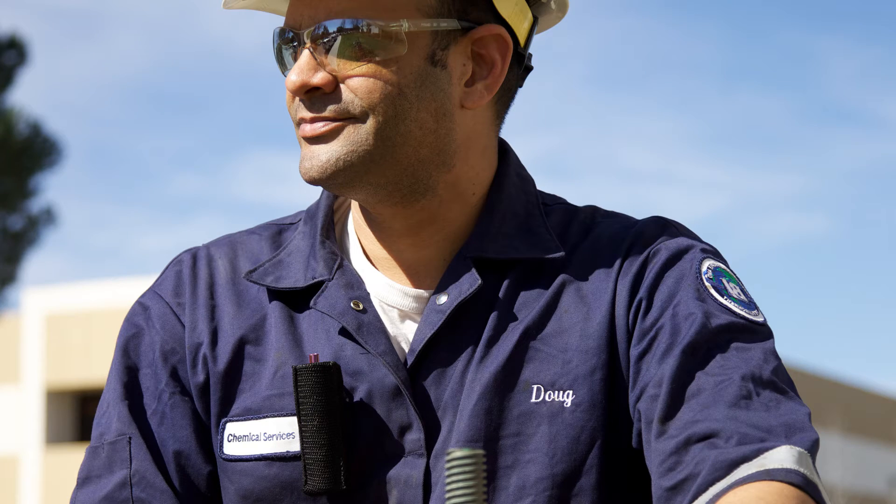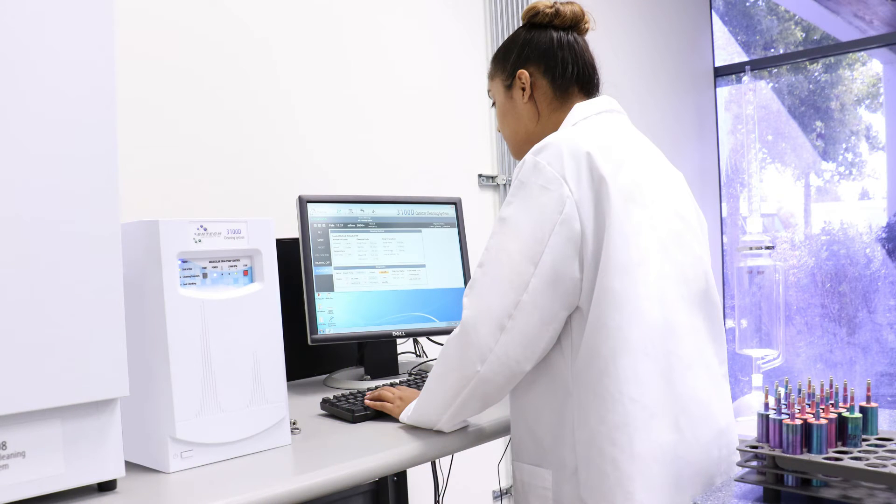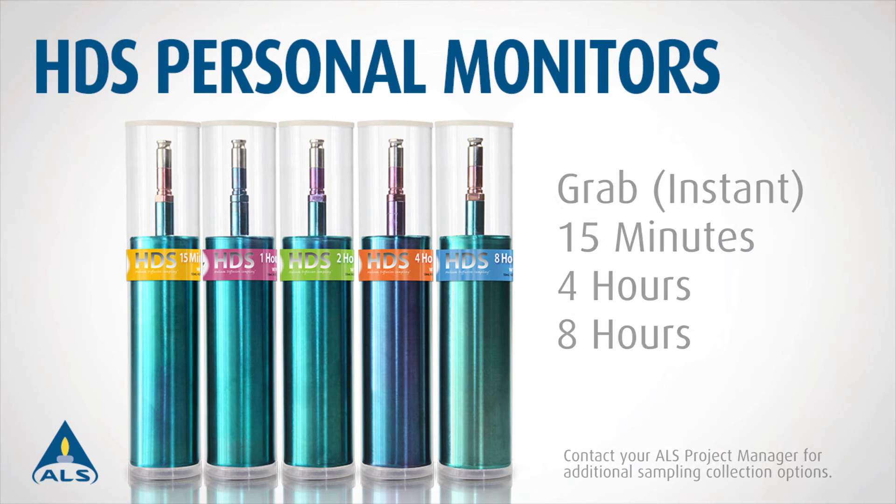The size of the HDS personal monitor makes it more convenient to carry than a SUMA canister and is extremely reliable, providing detection limits five to seven times lower than organic passive badges or charcoal-based sorbent tubes. Sample collection times using the HDS monitor include grab, or instant, 15 minutes, 4 hours, and 8 hours.